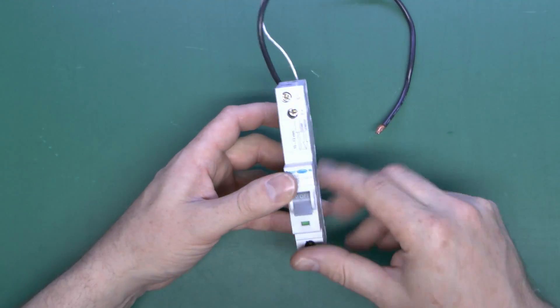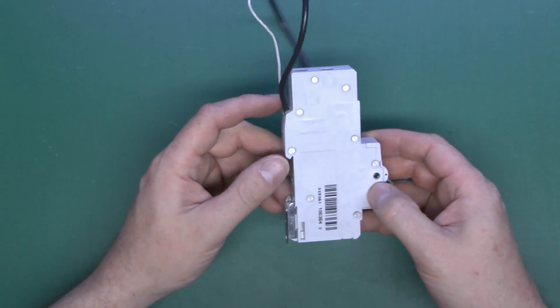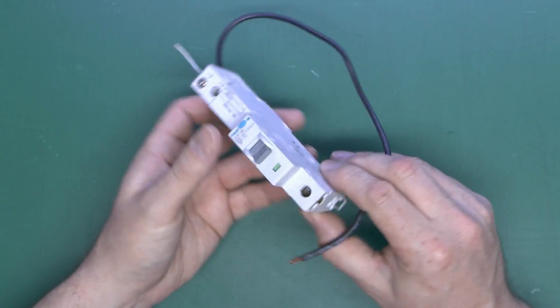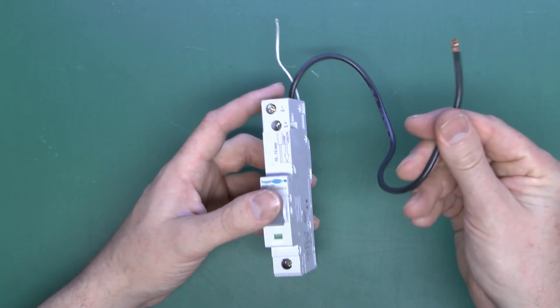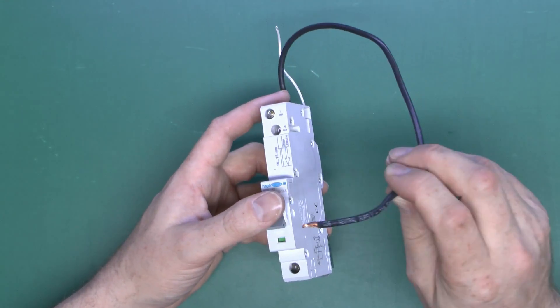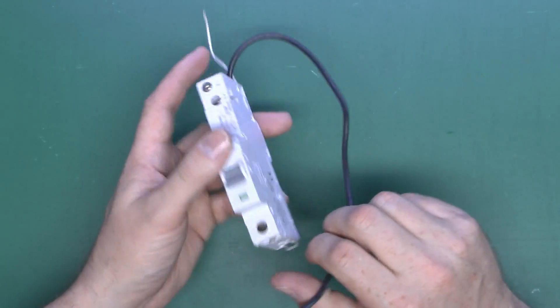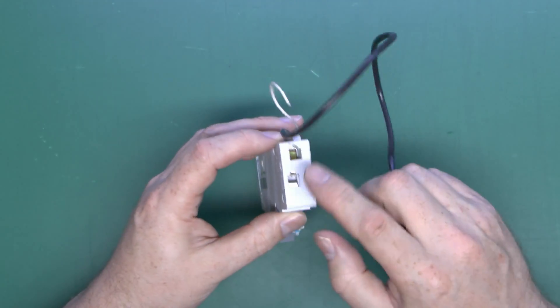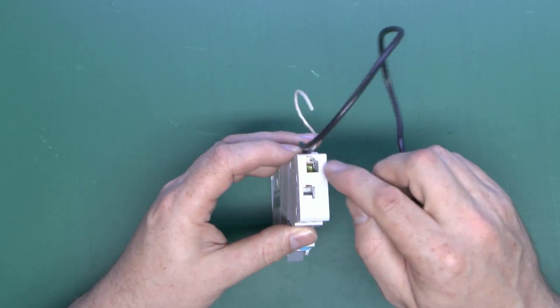Now here we have an RCBO, which is the circuit breaker and RCD combined into a single unit. And in common with most of the single pole versions of these, the neutral connection is on this separate lead, so line goes in at the bottom, and then the neutral is on this black lead in this case. Circuit wiring on the line and neutral connects at the top.